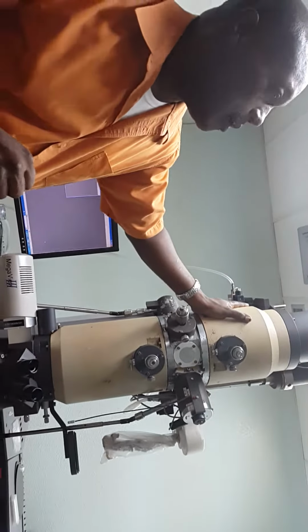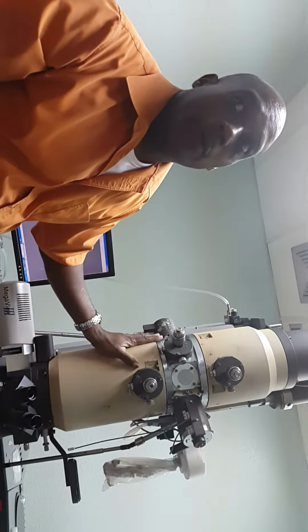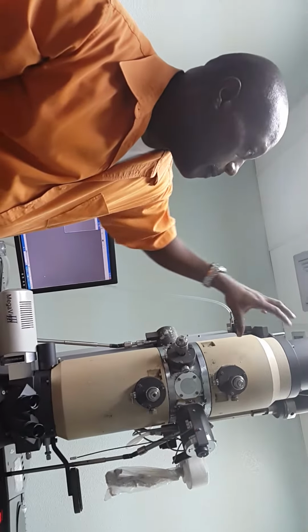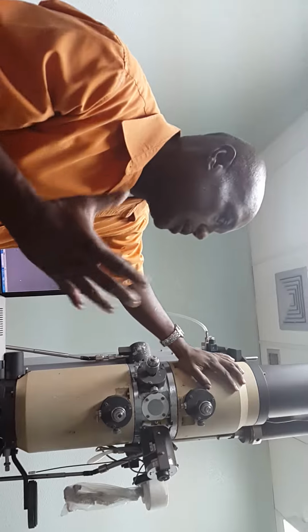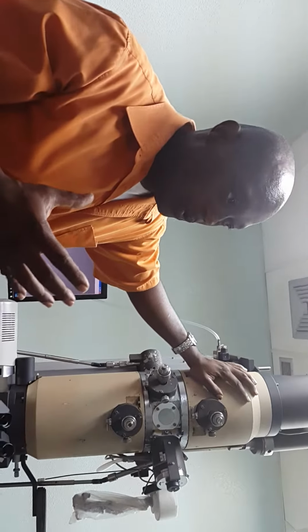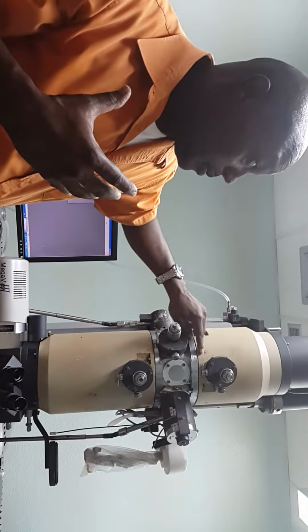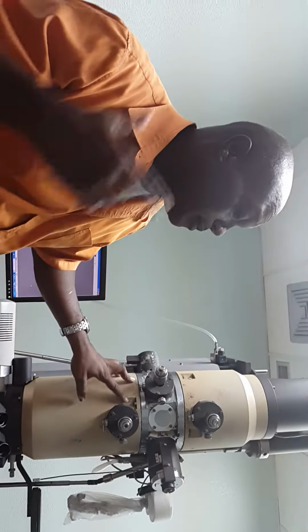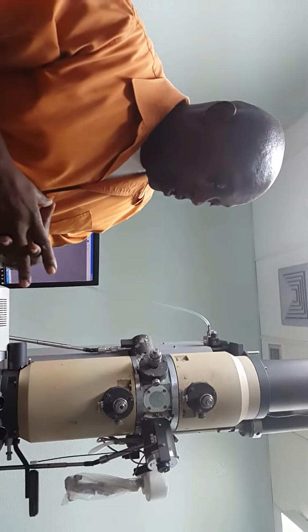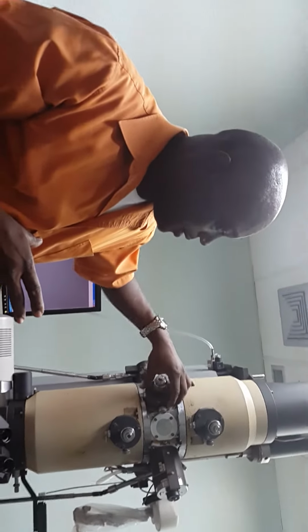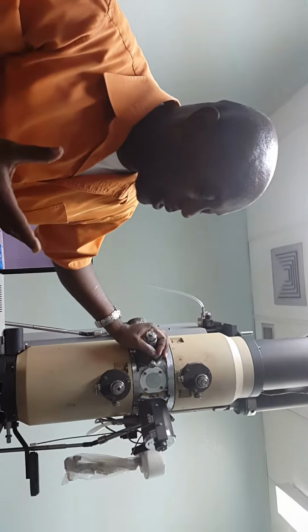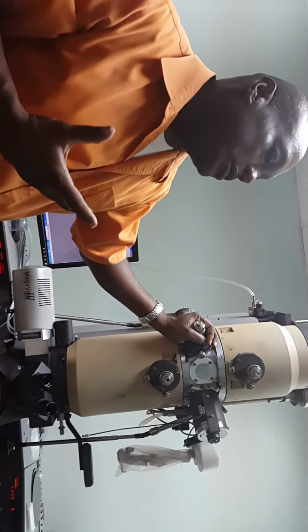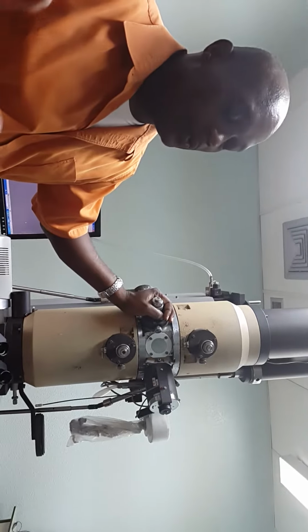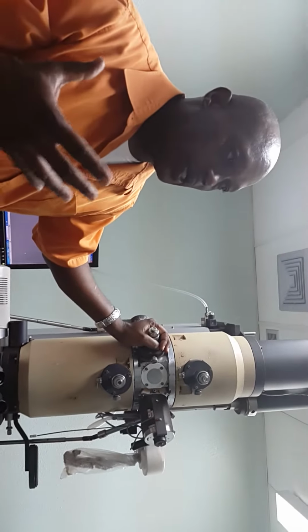There is water circulating through these lenses to keep them cool. The lens temperature and the atmosphere in here have to be the same temperature, or else you get drift, or condensation. I was getting condensation because I had heat coming into this room. Then the vibration: these rooms are usually called dead rooms because you try to have no vibration, no atmospheric vibrations or anything like that.